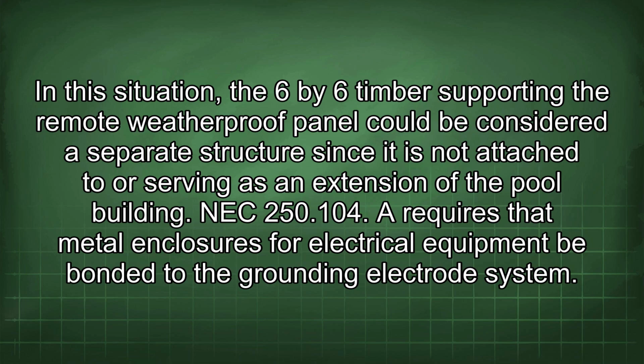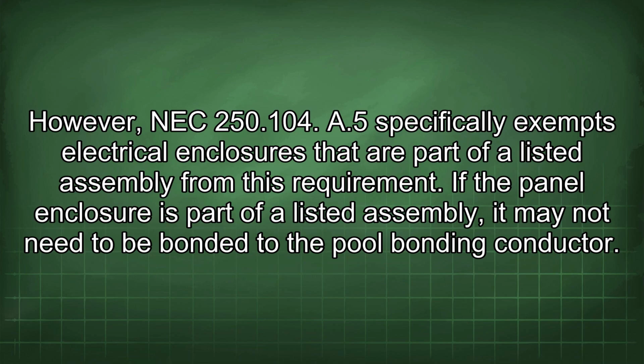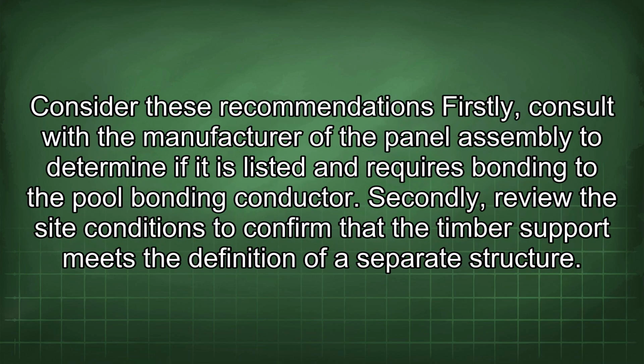NEC 250.104 requires that metal enclosures for electrical equipment be bonded to the grounding electrode system. However, NEC 250.104 A5 specifically exempts electrical enclosures that are part of a listed assembly from this requirement. If the panel enclosure is part of a listed assembly, it may not need to be bonded to the pool bonding conductor. Consider these recommendations.